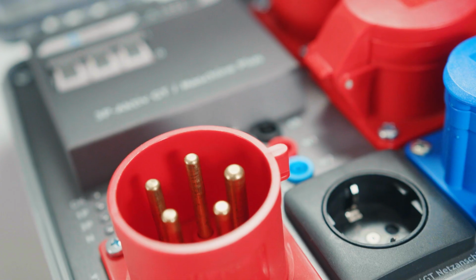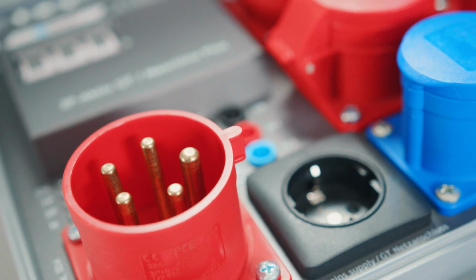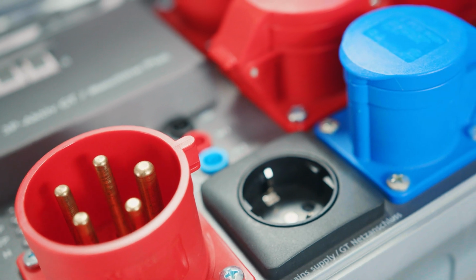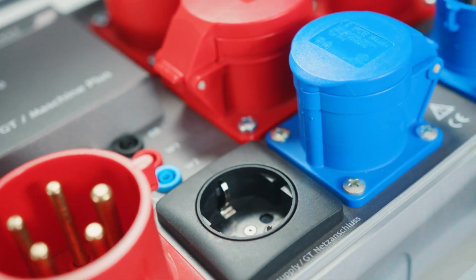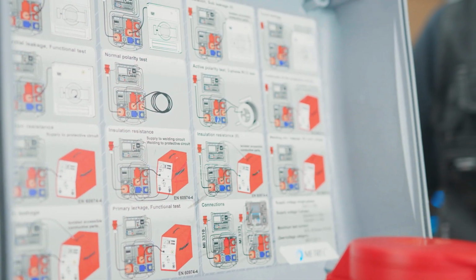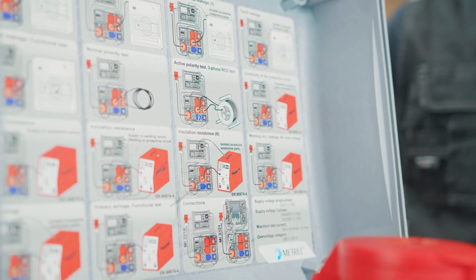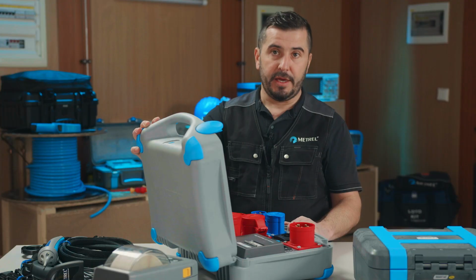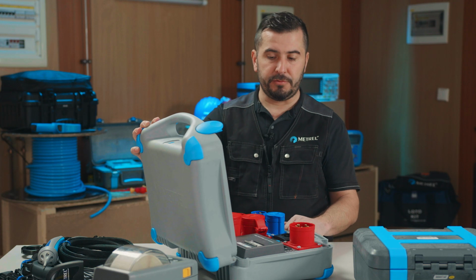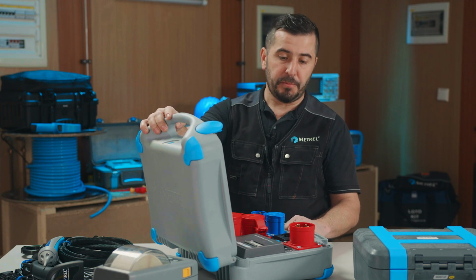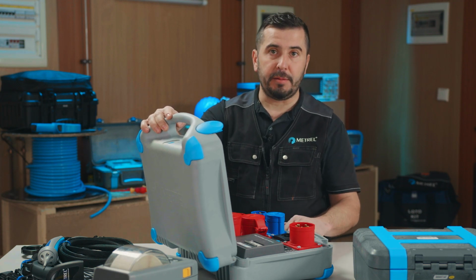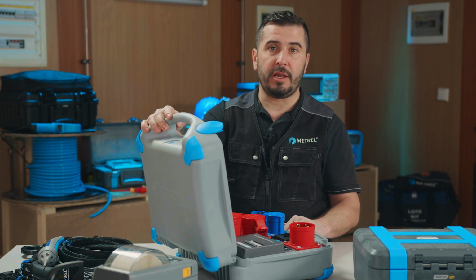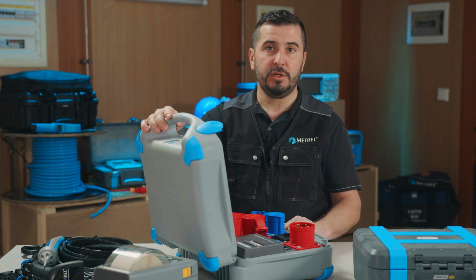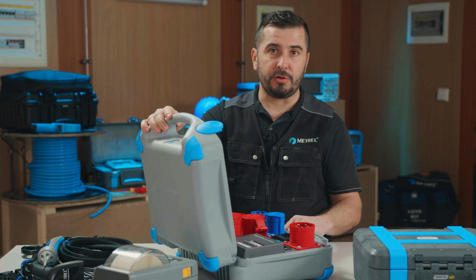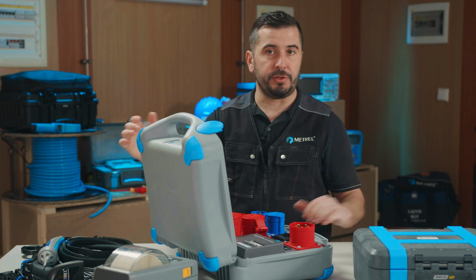So you can see that it is equipped with 16 amp, 32 amp, and also these single-phase sockets. So basically you can connect every possible appliance to the tester. And what is also a very good feature is that the three-phase adapter itself can do live leakage testing up to a current of 40 amps for a duration of 10 minutes.